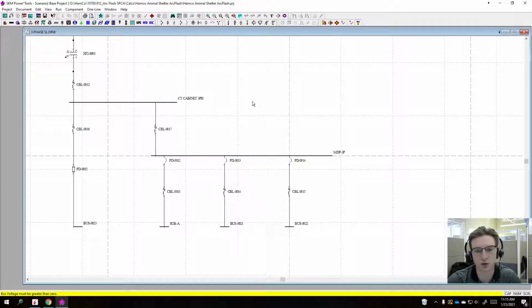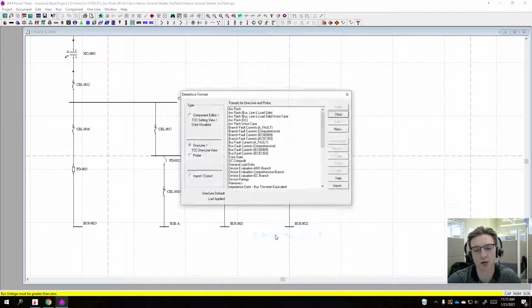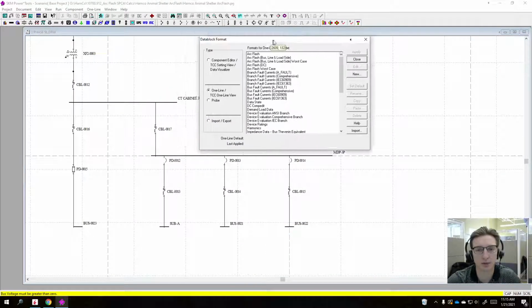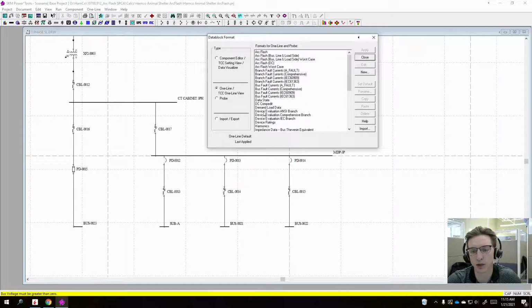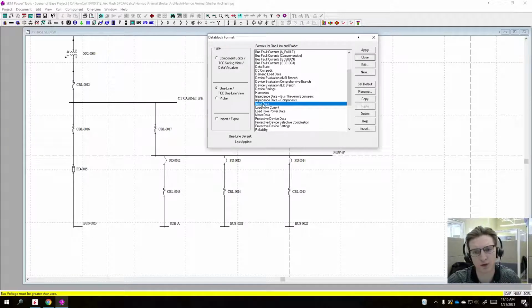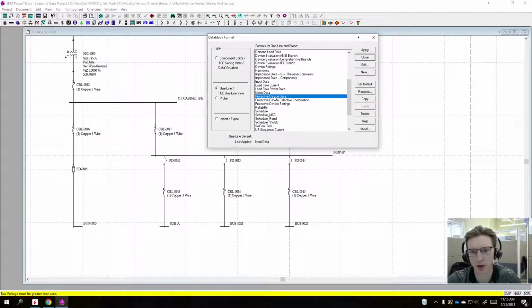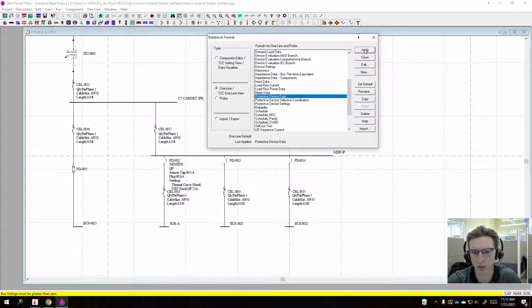So you just right click on the background, go to data block format. This might take a little trial and error, but we're going to do input data first, hit apply, and see what that comes up with. That seems to only be bringing in transformer data and wire information. So instead, I'm going to try protective device data, and that seems to be bringing in everything that we want.